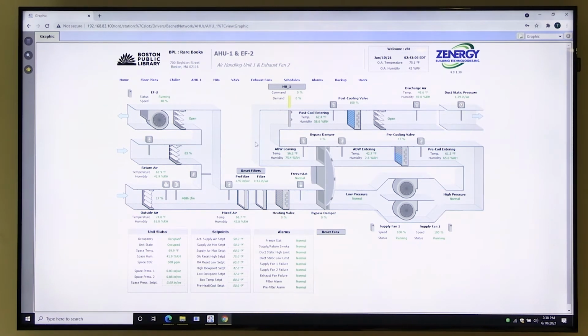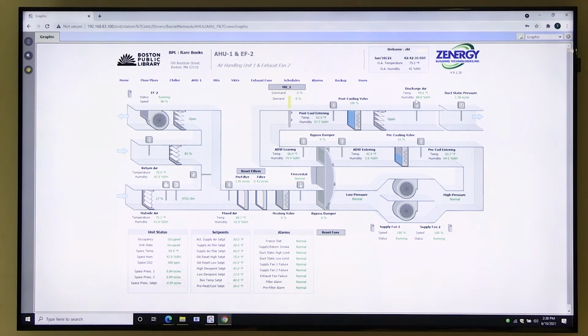So kind of going back to our exercise before, when you went to a VAV, the space was hot, there was no airflow. Well, maybe there was airflow, but the temperature was hot. So you went to the air handler to see what it's doing. You came here and the fans are running great, everything seems fine. These two coils are full blue and 100%, but your temperature is 80 degrees. Well, you probably have a chilled water problem. So you either have a problem with your chiller that's designated just for this, or we're not pulling chilled water from the rest of the building.